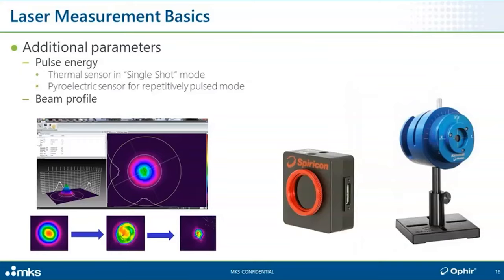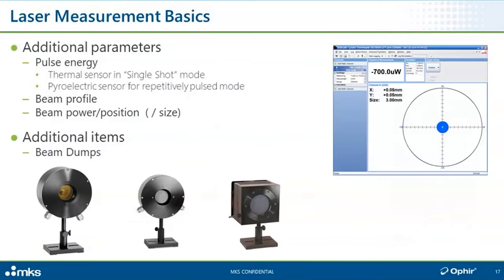All right, there are additional parameters that we're, again, not going to get into today, but I have to mention them. The beam profile is very often extremely critical. I mean the spatial distribution of the power through the beam cross-section. That affects the focusability, if there's such a word, of the beam and the shape of the focal spot and therefore of the cut or the hole or the weld and so on. As you well know, we have solutions for measuring the beam profile of high power beams way beyond the scope of today's discussion. But I have to mention it. Additional parameters, pulse energy. If we're dealing with a pulse beam, a lot of welding applications make use of the energy per pulse as opposed to the average power. There are solutions for what we might call quick and dirty measurements of the beam power position and size without necessarily getting information about the actual spatial distribution within the cross section, just the size.